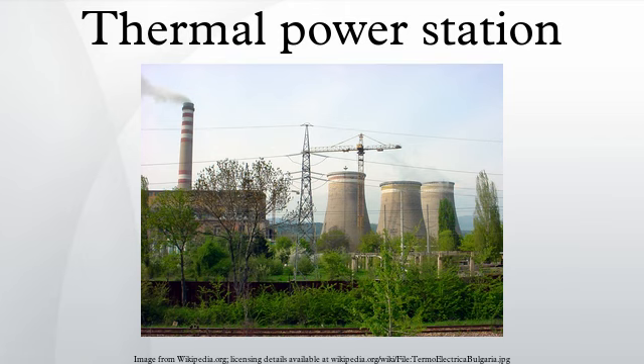The generator, 30 feet long and 12 feet in diameter, contains a stationary stator and a spinning rotor, each containing miles of heavy copper conductor. No permanent magnets here. In operation it generates up to 21,000 amperes at 24,000 volts AC as it spins at either 3,000 or 3,600 RPM, synchronized to the power grid. The rotor spins in a sealed chamber cooled with hydrogen gas, selected because it has the highest known heat transfer coefficient of any gas and for its low viscosity, which reduces windage losses. This system requires special handling during startup, with air in the chamber first displaced by carbon dioxide before filling with hydrogen. This ensures that a highly explosive hydrogen-oxygen environment is not created.